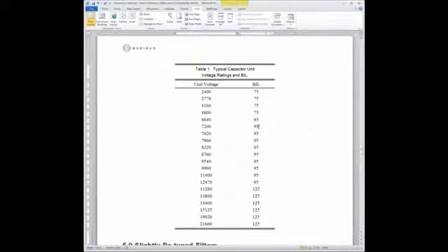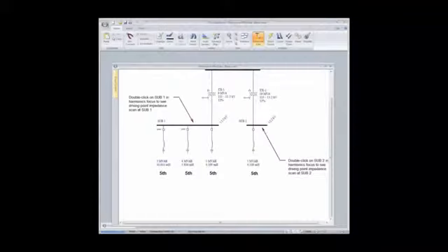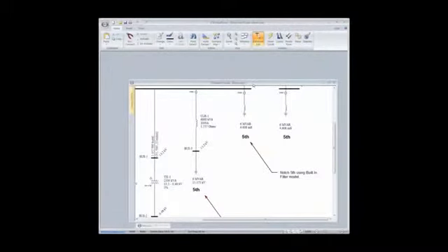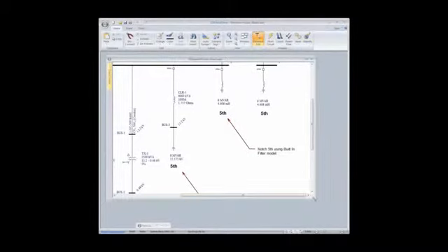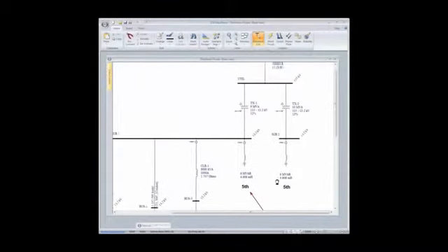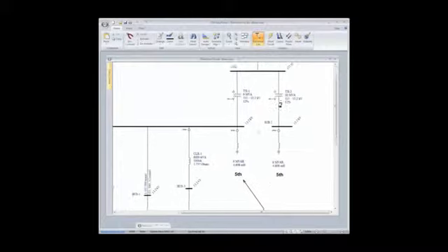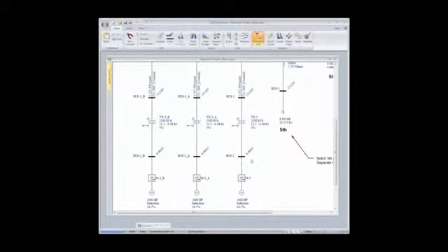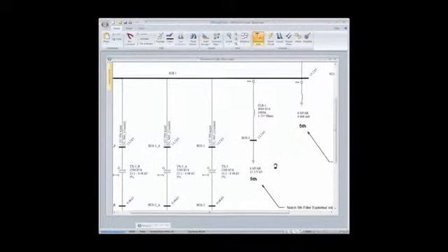Okay, one of the things that will happen, and let me switch this over to EasyPower again, in your systems, when you have a harmonic filter application on the bus. And so I have this distortion fix example. It's very similar. The only thing I've added to this is some harmonic load down here so I can get some distortion.